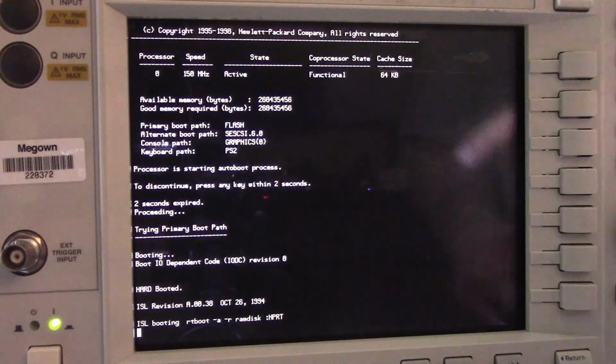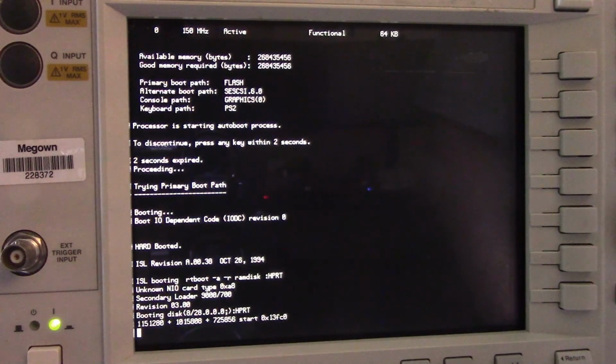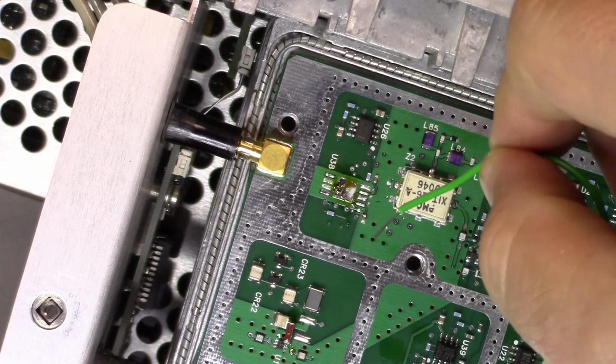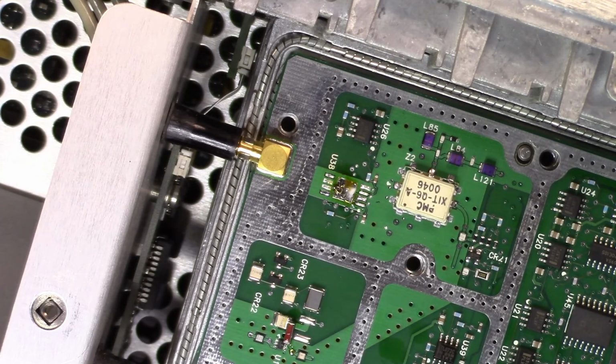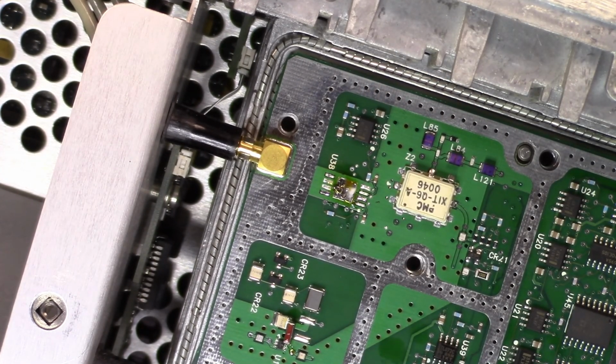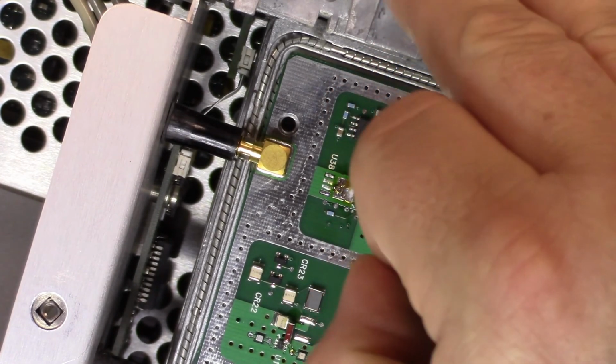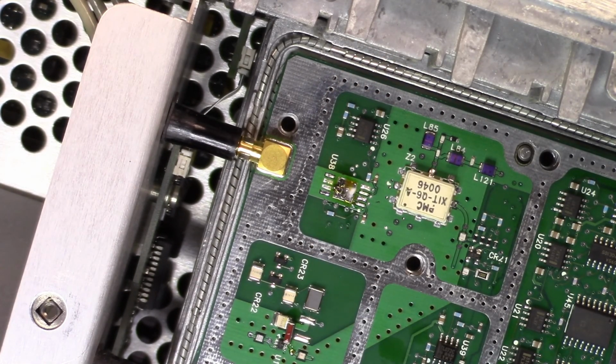Now, you'll see here that it's booting up, and when it undergoes its self-test, it'll fail the self-tests here, which is what it should do, because what it does up here is it changes that calibration signal into this stage in and out as it's testing, and it can't do that clearly because it has no actual relay there. So I think that when it was doing that test, it was coming up and configuring itself, and the relay was giving it the 50 cal signal okay, but it wasn't giving it the external signal. So let's just wait for it to finish booting, and then we'll just do a raw test to see if the rest of the system is going to read a value correctly.